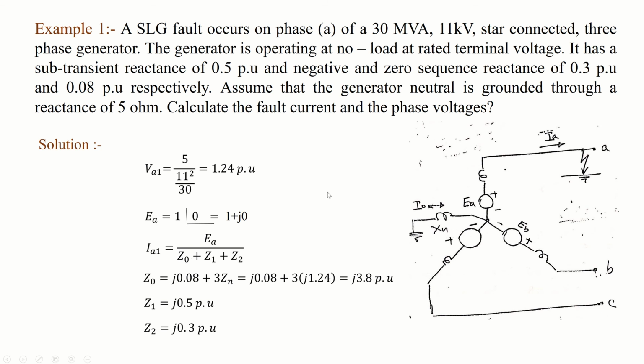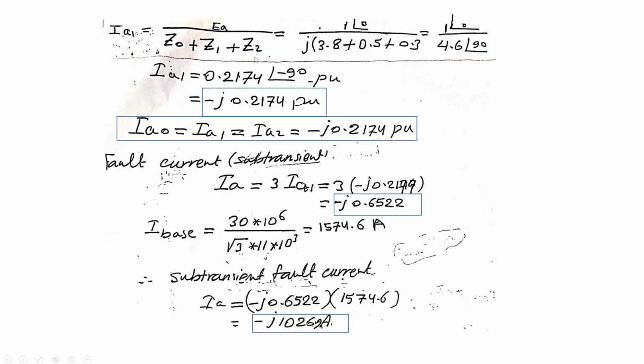This Z0 is 0.08 plus 3XN, so 3XN, 1.24 multiplied by 3, or ZN. So you will get Z naught. Z1 is 0.5 and Z2 is 0.3. Now you apply this formula, add all this together, and you will get IA1, which is equal to IA0 and IA2. To calculate the phase current, which is 3IA0 or 3IA1, you divide 3 by this value, and you will get the fault current in per unit.